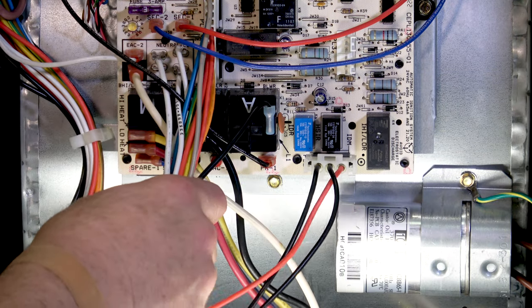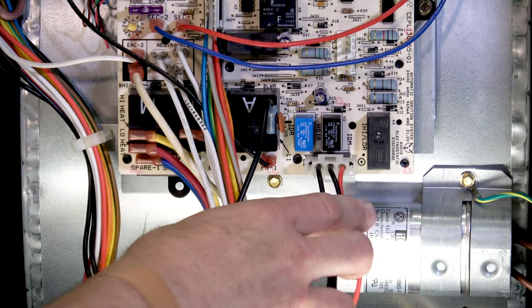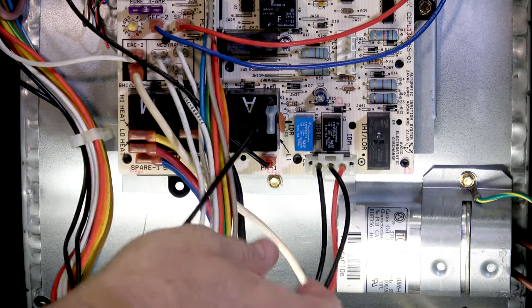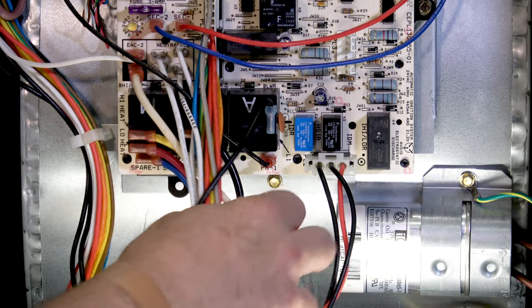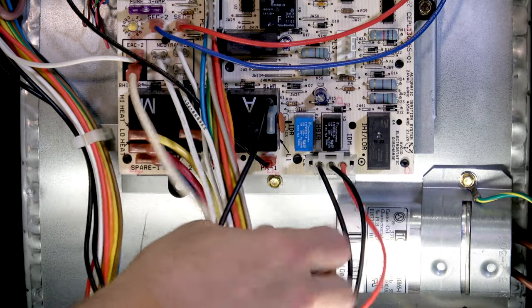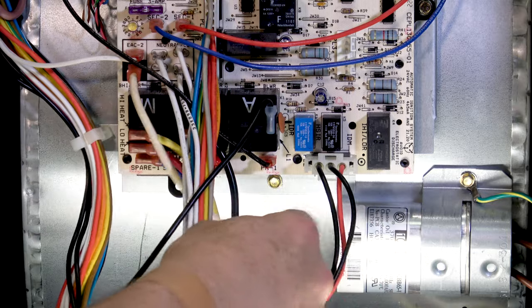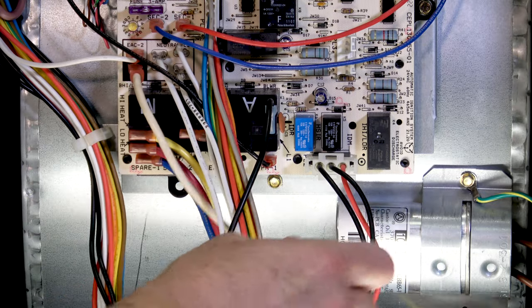Now we're in the blower section of the furnace. This is our blower assembly. This motor that we're dealing with here is a four-speed motor. We have our four wires and then our fifth wire is our neutral wire.